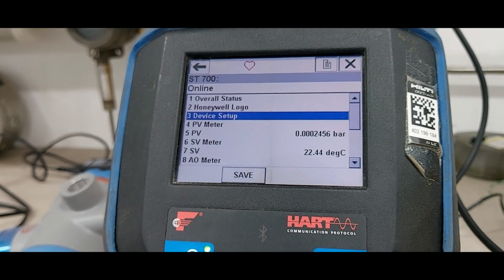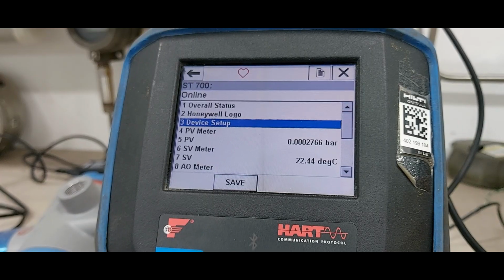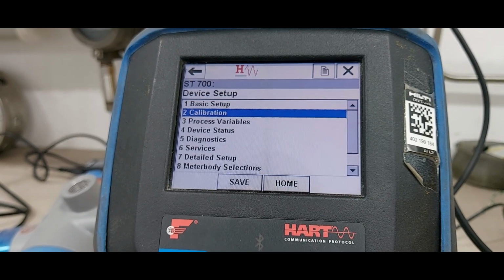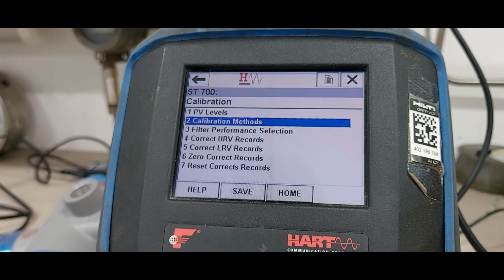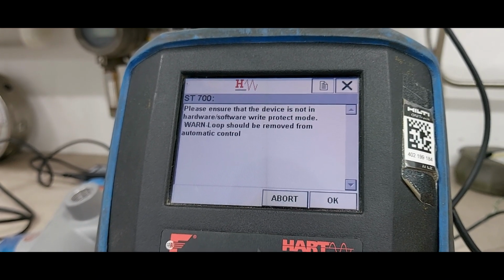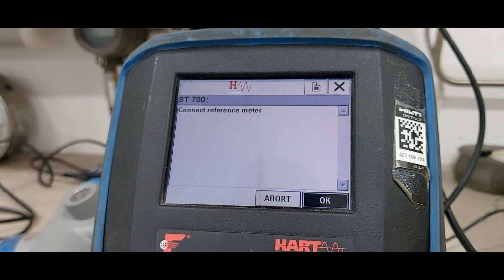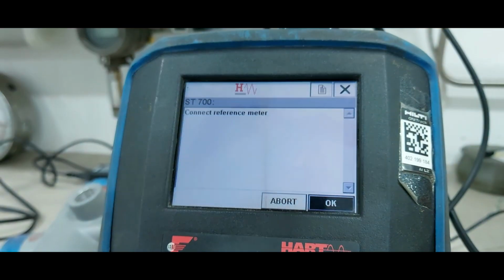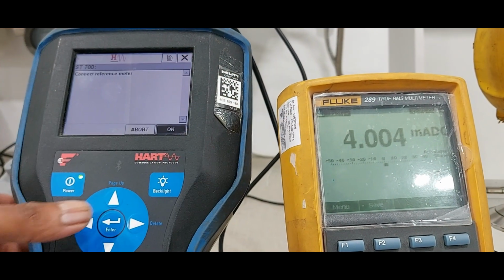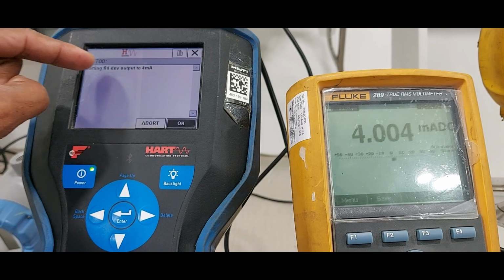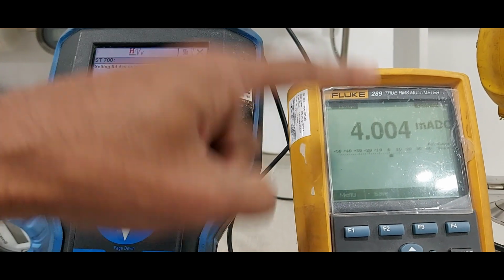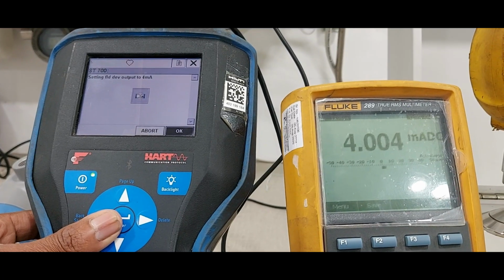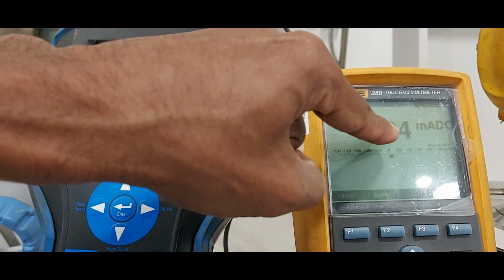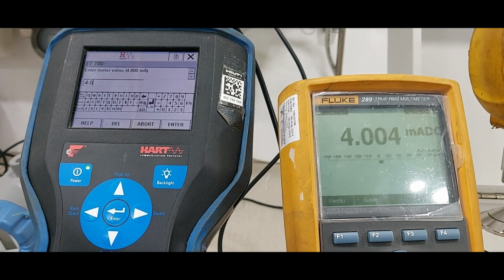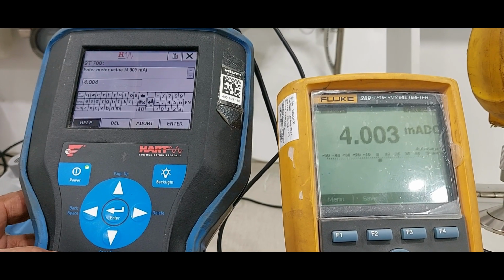Next we are doing the DA trim calibration, digital and analog calibration. Select the calibration methods, DA trim. Then OK. Connect the reference meter. Reference meter already connected. Then press OK. Okay, set the field value. Output showing 4 milliamps. That is also fine. Okay, set the field value output value. That is showing 4.004. Enter.